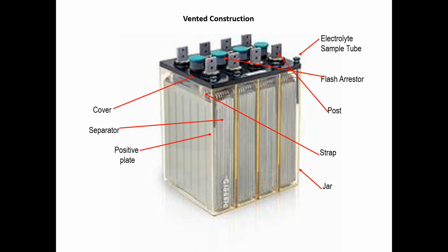But the idea here is a lot of these same components, strapping, jar, positive plate, that's common to all battery designs. I'll say an advantage to this particular design is it's a jar you can see through. So you can look at sediment buildup at the bottom. You can look at plates for crystallization or sulfation. You can look for corrosion inside, the battery separator falling apart. And then it also has additional ability to sample the electrolyte, so you can look at the state of charge of the battery. You can also, along with this battery, you have to periodically add water to the electrolyte.